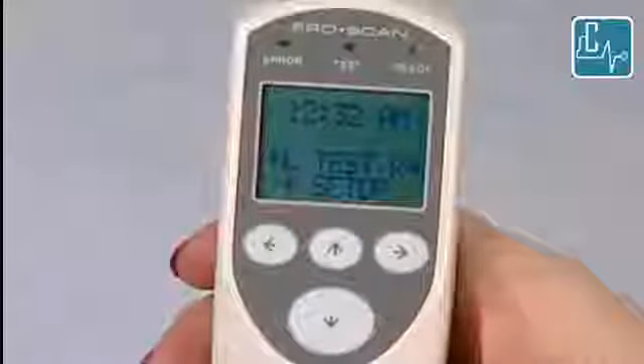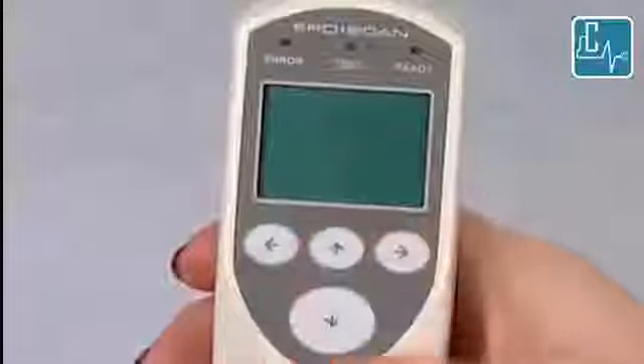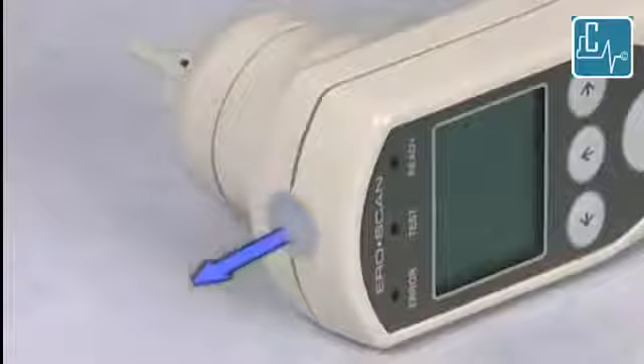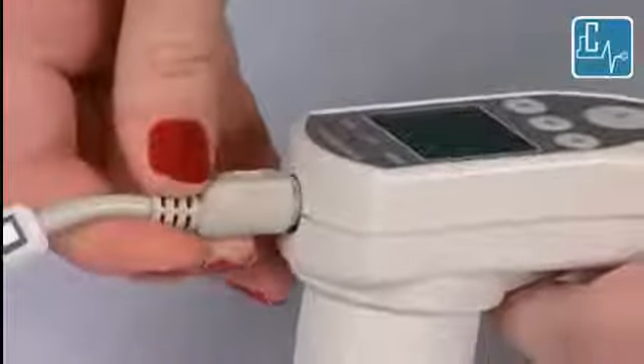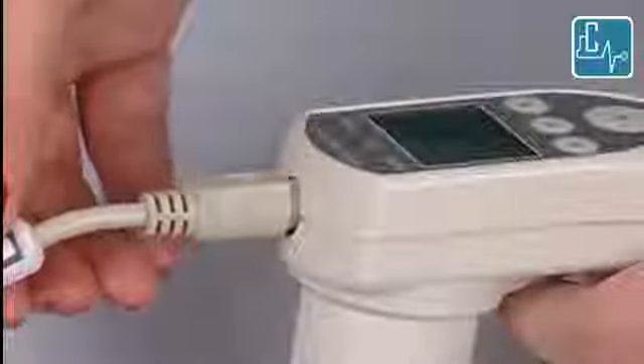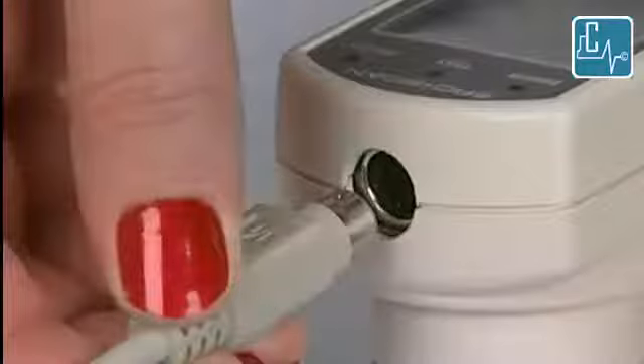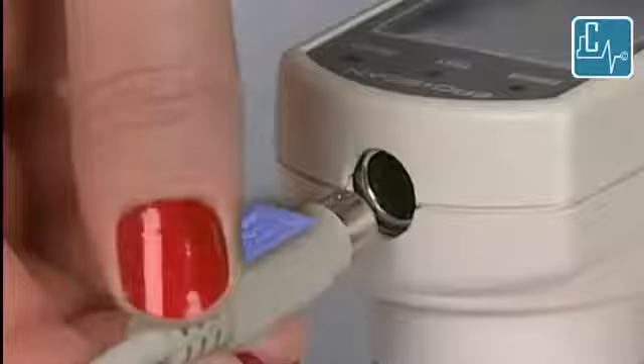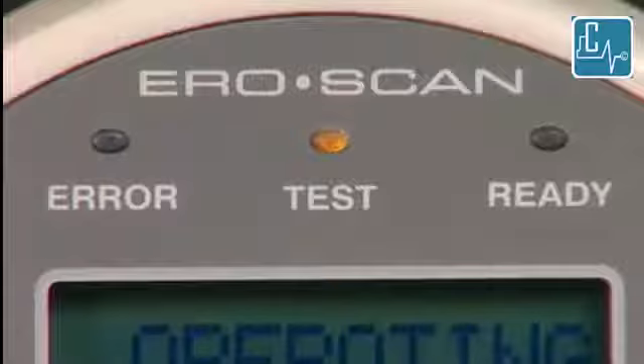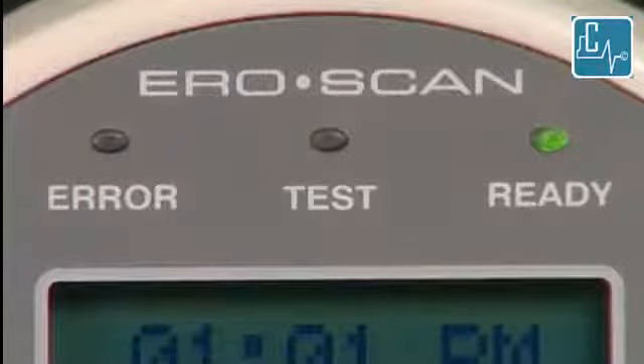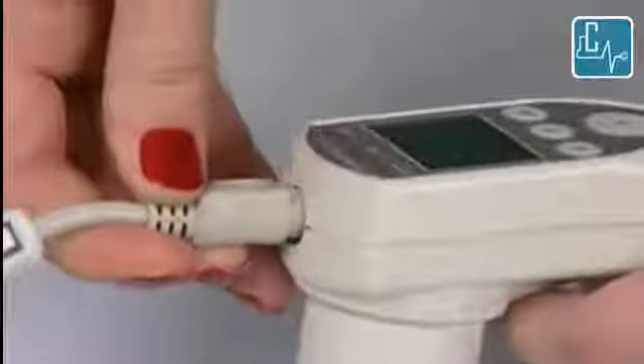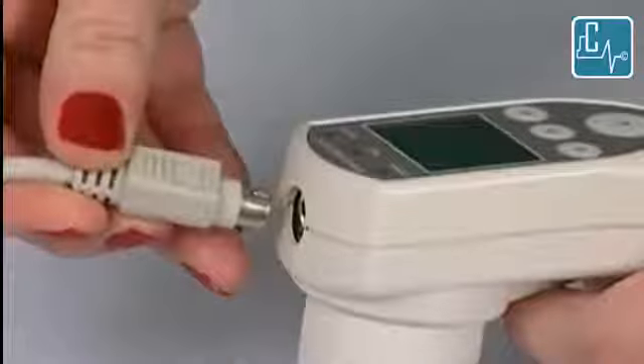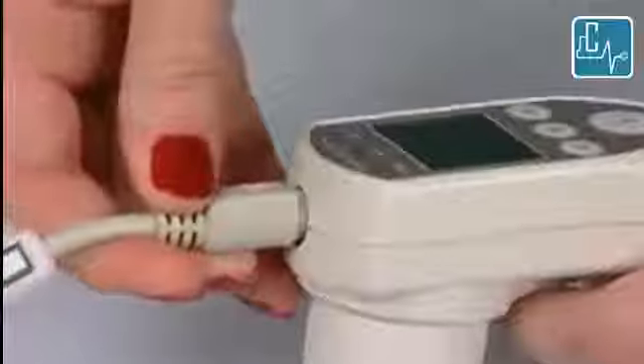To use the external probe, turn the ERO.SCAN off and remove the protective cover from the top of the unit. Next, plug the external probe connector into the external port. Take care to align the connector with the flat side facing the display. When turning on the ERO.SCAN, the yellow test light will illuminate briefly to indicate ERO.SCAN has detected the presence of the external probe. If the yellow light does not illuminate, remove and then reconnect the probe.